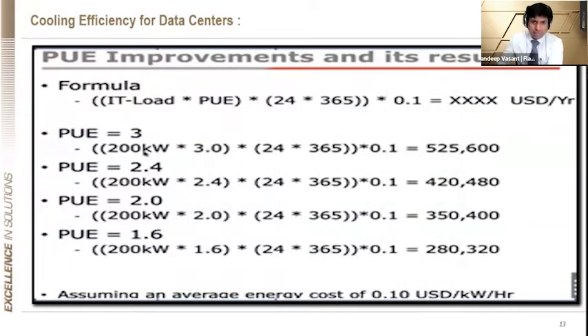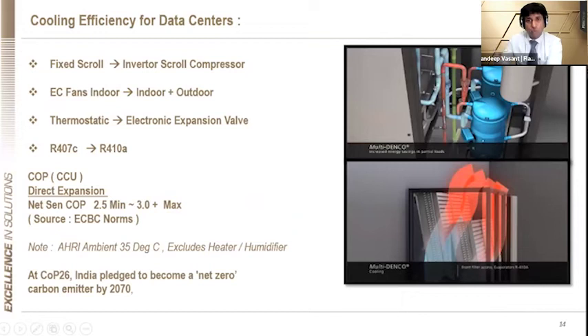Going to the next slide, as I said, the lower the PUE, the more efficient. Basically, if you see a PUE of 3 vis-a-vis a PUE of 1, if you do simple math, close to 40 to 50% is the saving. So we need to focus on the PUE and on the HVAC at 30 plus 8, 38%. We saw the precision air conditioning unit which sits in the data center. Number one is we need to select the best, most efficient components. As I talk, you can see the inverter compressor. Earlier we used to use fixed, but now it's a request that everyone looks at an inverter compressor.